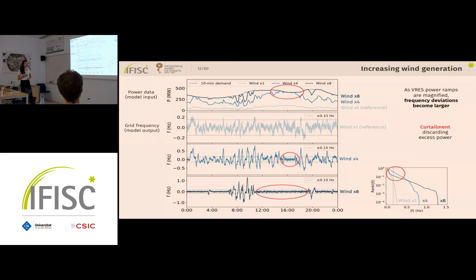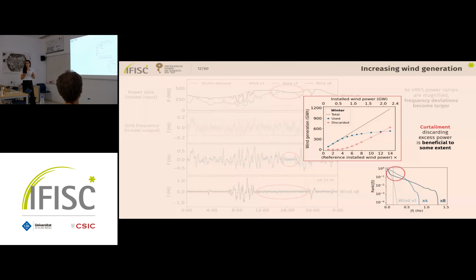And of course, this is beneficial, but only to some extent, because in the end, we are discarding power. So at some point, when increasing the installed wind power further, the discarded power increases more than the used power does. So at some point, it's not really worth it. So as we saw before, these frequency fluctuations in these scenarios with larger wind generation are way too large. They exceed this 0.15 Hertz limit.